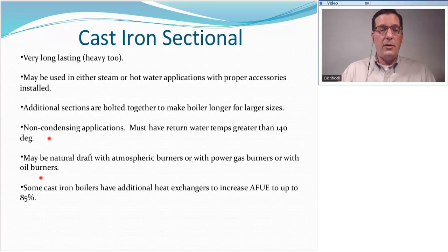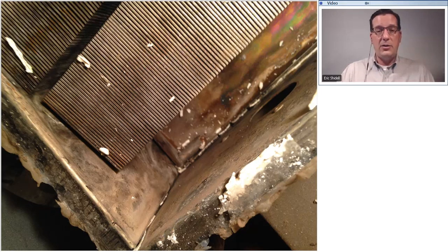Cast iron sectional boilers may be natural draft with atmospheric burners, or they may have power gas burners or oil burners or coal or some other fuel. Some cast iron boilers have extra heat exchangers, and this is meant to increase their annual fuel utilization efficiency up to about 85%. And on our next page is a picture of one of those extra heat exchangers. This is the top looking down with the flue collar removed on a Weil-McLain HE series boiler, high efficiency. And that took their standard cast iron heat exchanger, put an additional heat exchanger on top of it to extract even more heat out of the flue gases, and this one will run at about 85% efficiency.